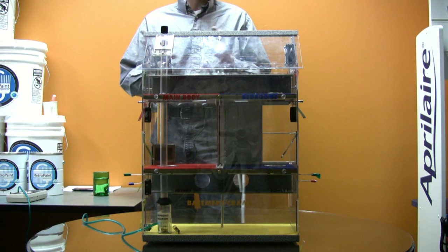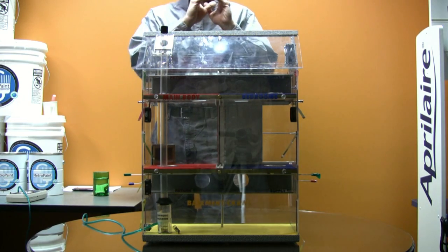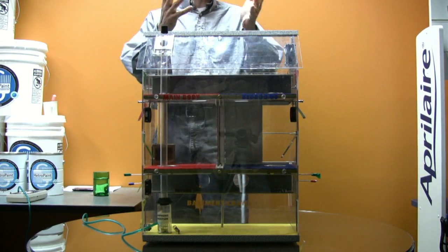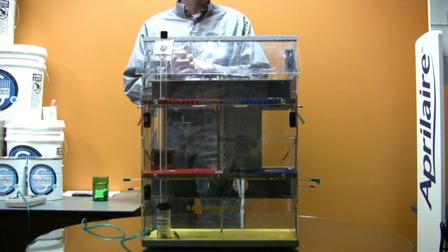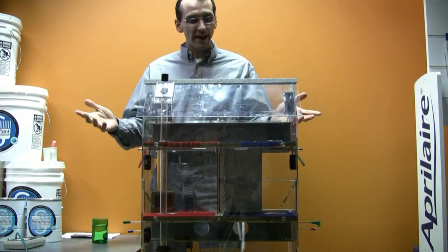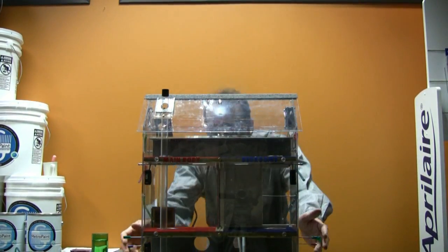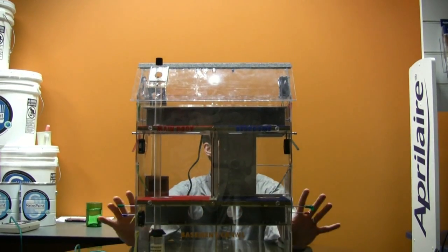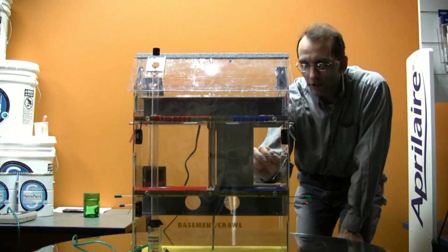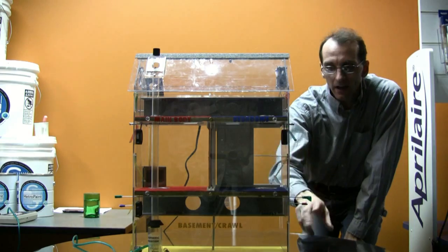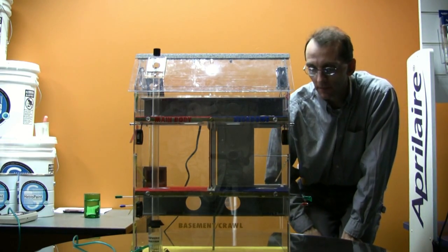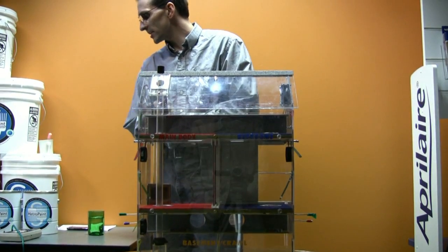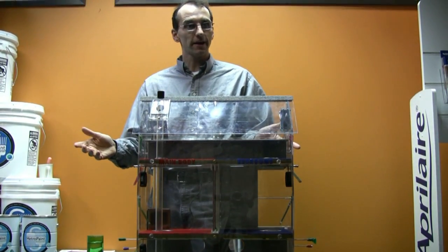Would a furnace have anything to do with that if it was in the basement? Yes. How could a furnace depressurize it even more? You turn the fan of the furnace on. If I leave both these ducts totally open, so I have a really leaky ductwork system, and now I turn the fan on for our furnace system, we've now gone to minus 1.4 pascals for that area.